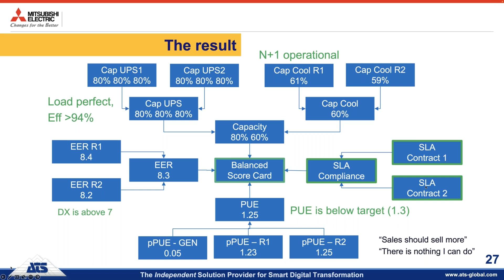Just an example, a co-location site, 12,000 square meters using 15 megawatts. They buy the energy at 10 cents per kilowatt hour. And if they have a PUE of 1.46, the yearly energy cost is $13 million. If they decrease that PUE from 1.46 to 1.25, the energy consumption is going to decrease from 15 to 12.8 megawatts. And then the total energy cost will be 11 million instead of 13 million. So that will bring $1.8 million yearly in energy consumption reduction.